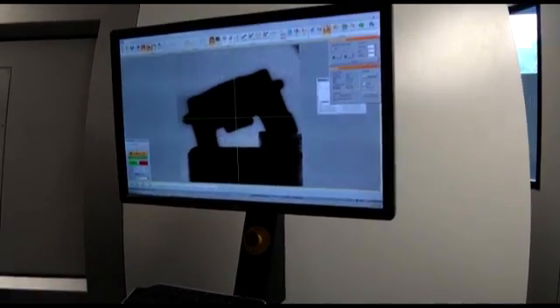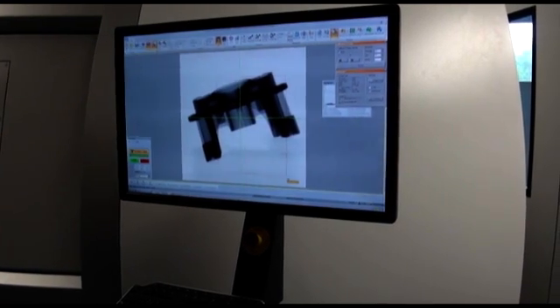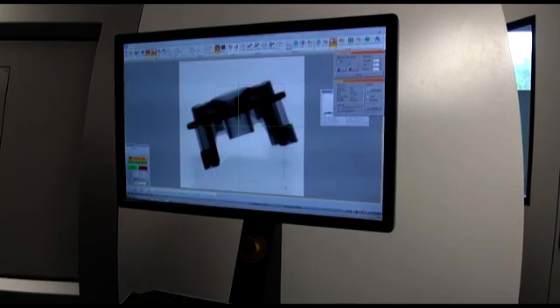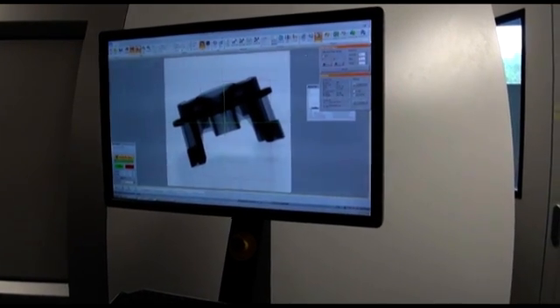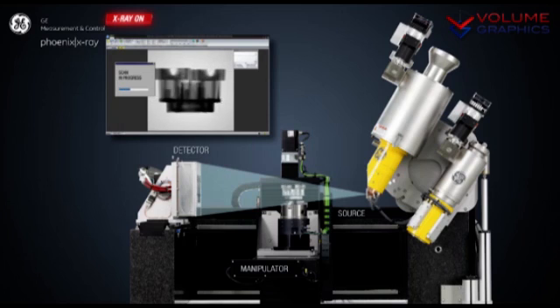When that is done I can verify that I have the right parameters and check the contrast settings on the image. We have good penetration, so everything is defined. I can then simply execute the scan by hitting the Start CT Scan button. The system now automatically performs all the necessary steps for acquiring the raw image data.